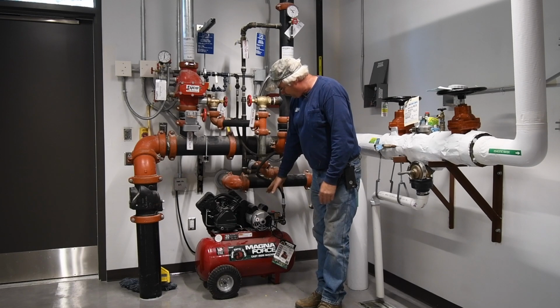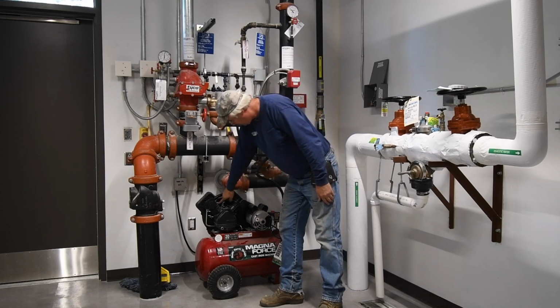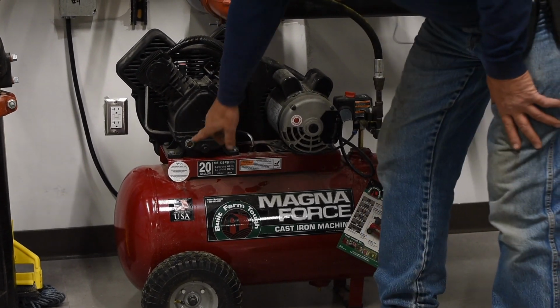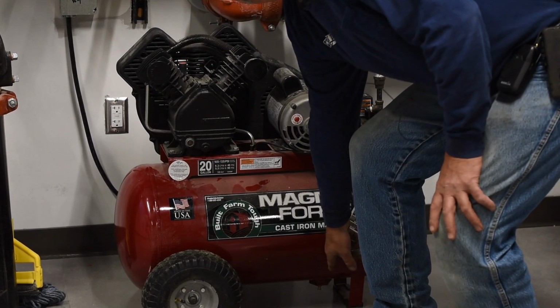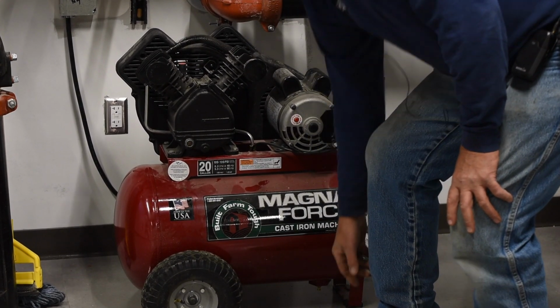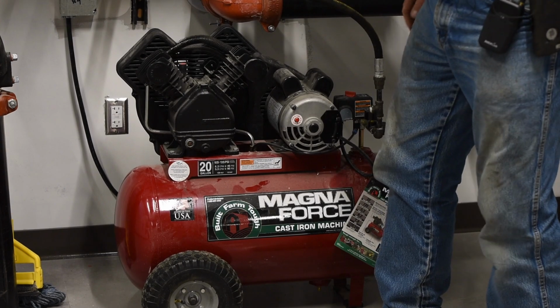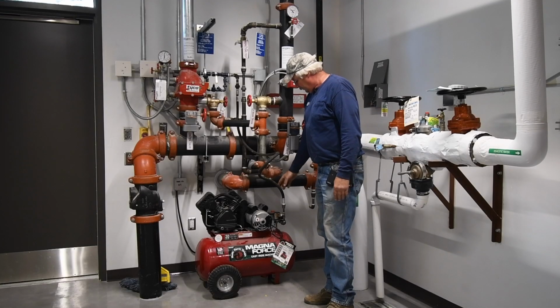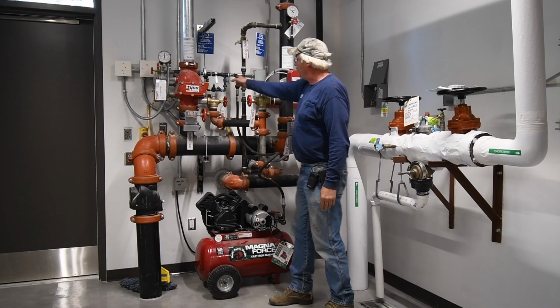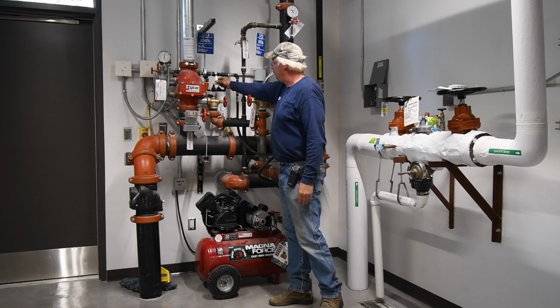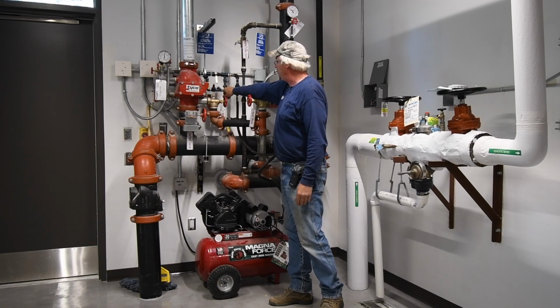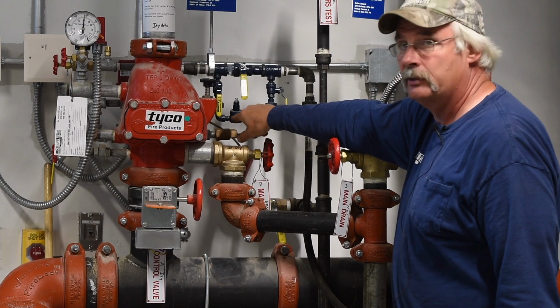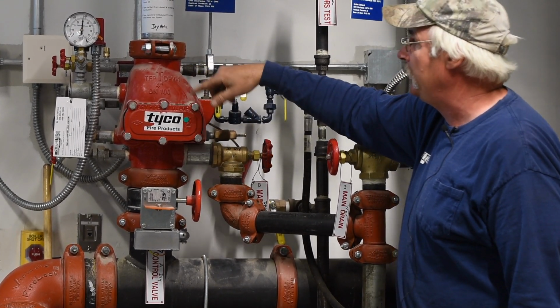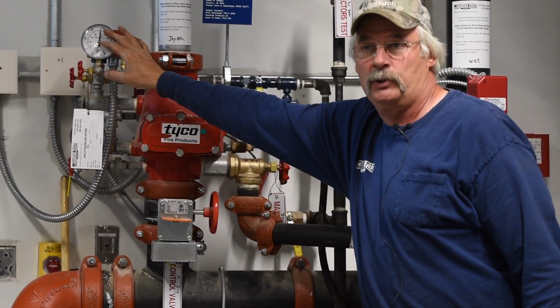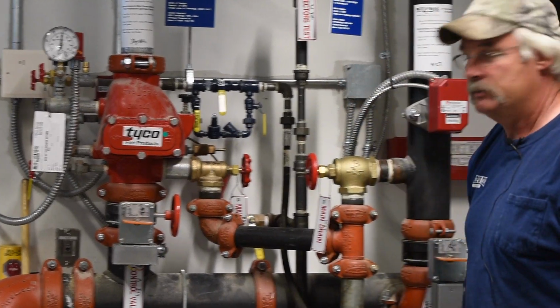And then we have an air compressor here. You can check the oil in it. There's an oil gauge, and right down below, for condensation, there's a little bleeder valve, you know, keep it dry. It's got a line coming up to an air maintenance device. This control valve here is normally closed. These 2 are open, and the air goes down through a restricted orifice through a regulator, to maintain air pressure in the system.